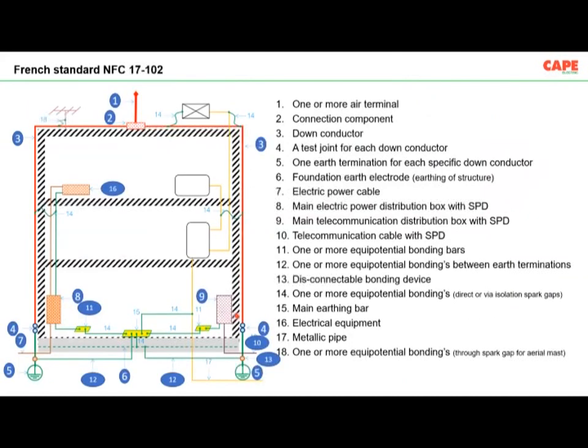There is an ESE standard which is called NFC. The standard of the French code explains it in this fashion. This picture is actually from the French code. It says you are supposed to make a perfectly equipotential bonded system. Over and above that, you can have an ESE rod. This is what it says. But the ESE manufacturer will never talk about this equipotential bonding. They always talk about one rod protecting 100 meters. This is wrong.